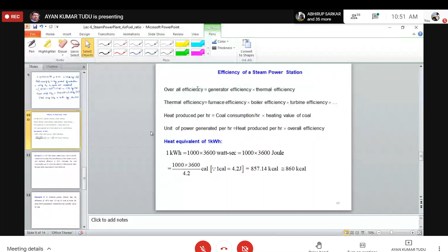The coal consumption per hour is nothing but the heat produced per hour divided by the heating value of the coal. So first of all, we have to find out the heat produced per hour. How can we find that out? For that, we need the overall efficiency. So first of all, the solution. We are finding out the overall efficiency. What is the overall efficiency of the station? It is equal to the thermal efficiency into the electrical efficiency. So how much is coming out? Thermal efficiency into electrical efficiency comes out to be 27.6%. Okay, so it is correct. Then what is the heat produced per hour?